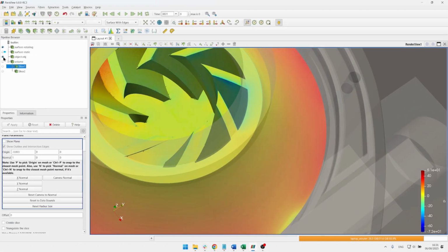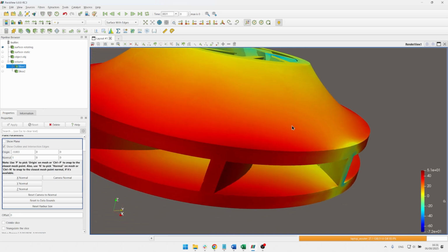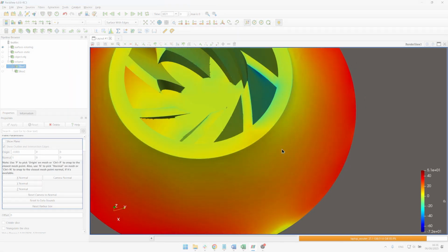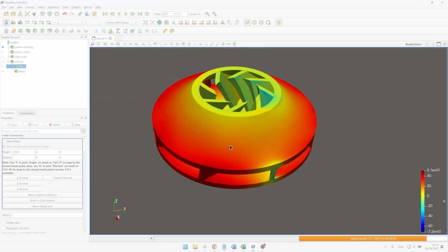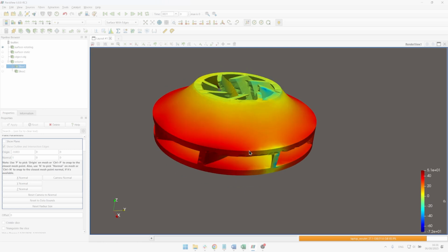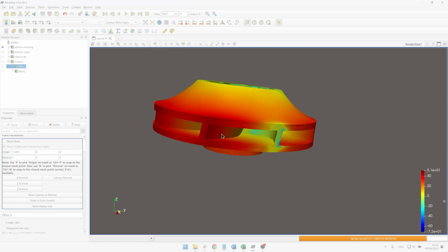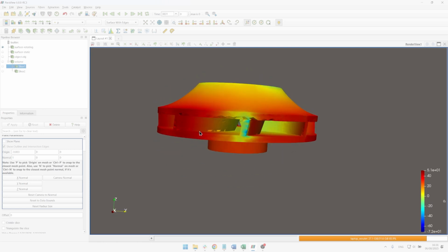Now, this is quite interesting. If I hide the housing for a second, what you'll see is that, first of all, the pressure rises as you travel along the radius, which is normal. This is where your pressure builds up as you move outward and the water gets slung towards the outside here. What's also interesting is that this is the direction of rotation, which means that the front of these impeller vanes are at high pressure, and the pressure rises as you go to a higher radius, because then, not the RPM, but the local velocity is simply higher.